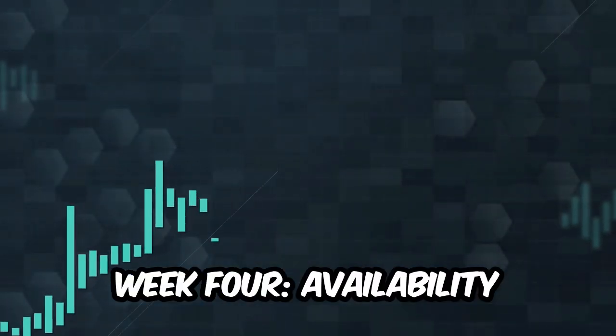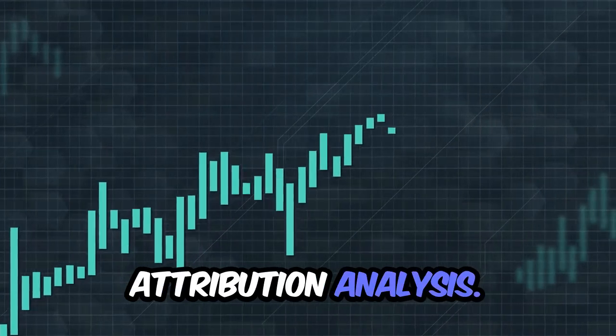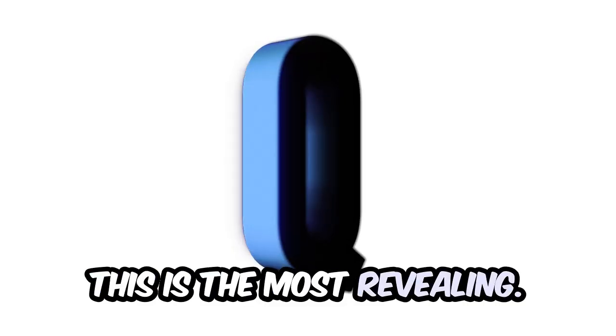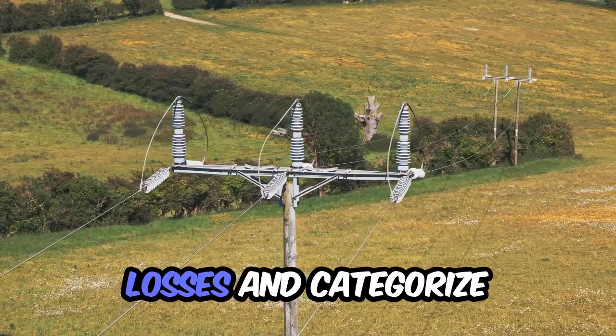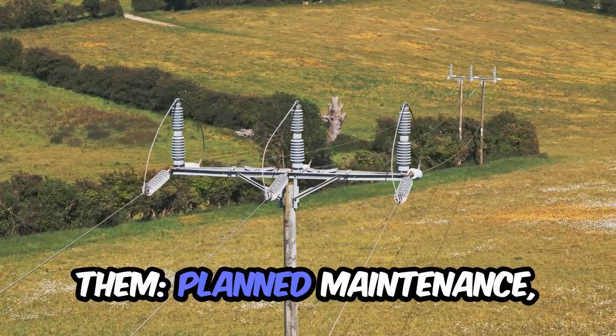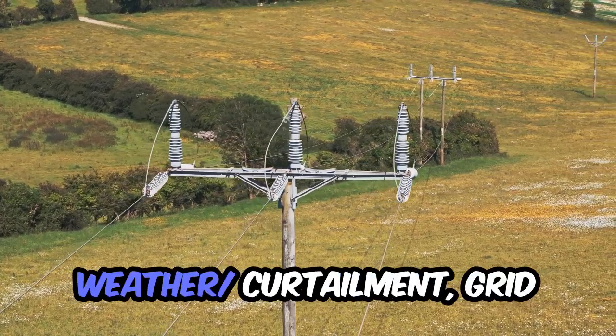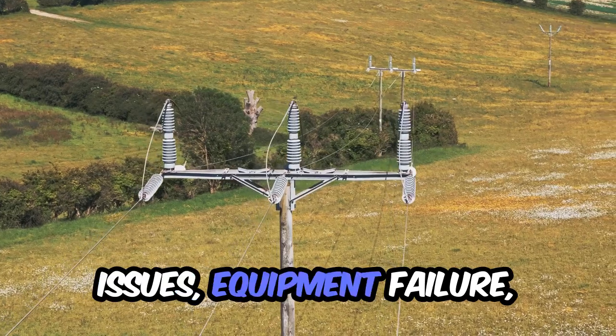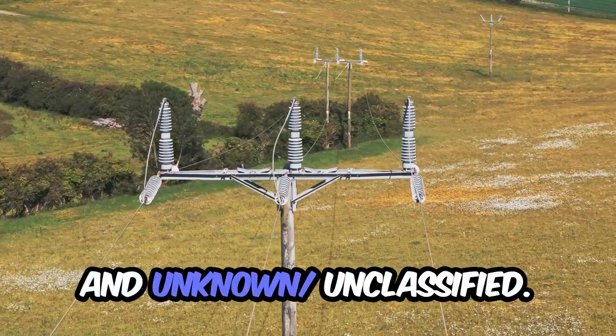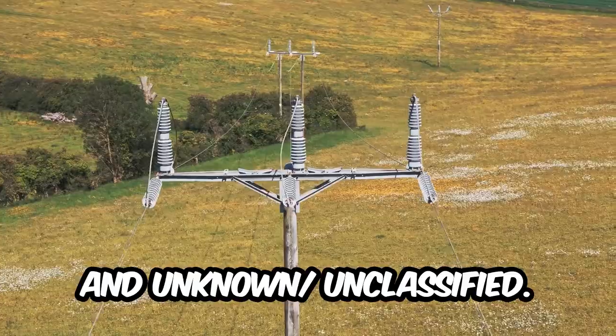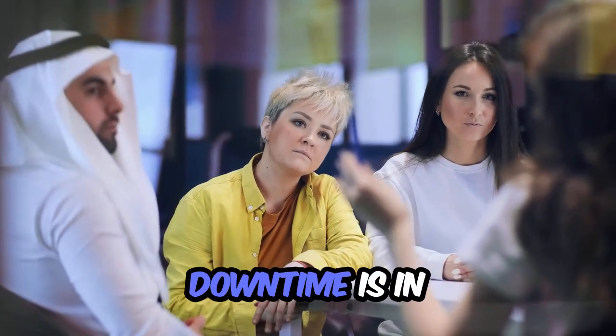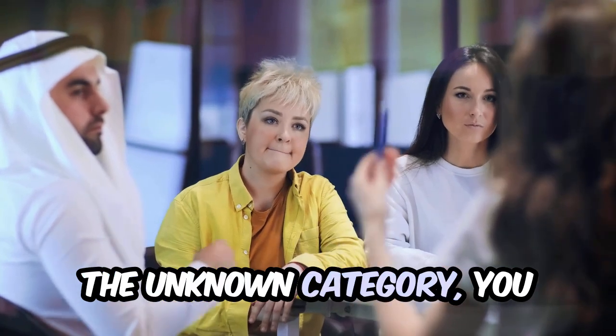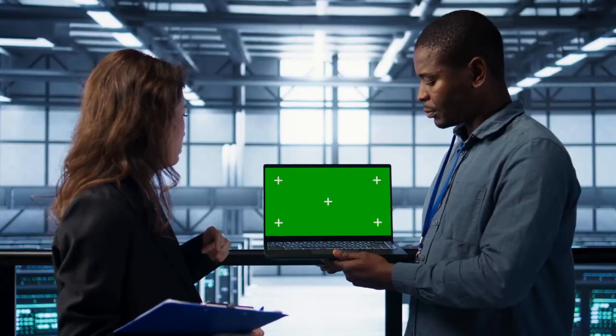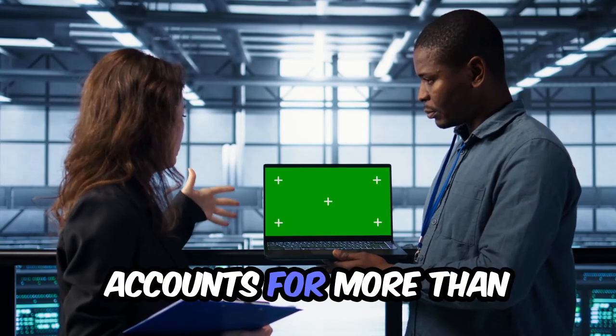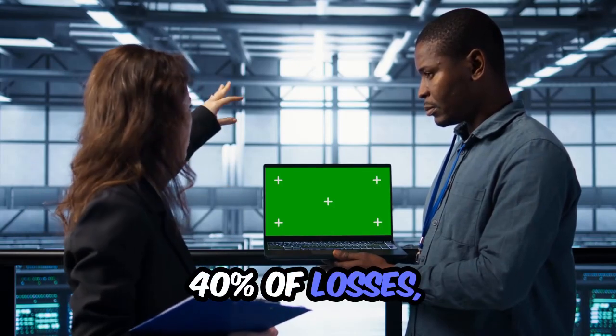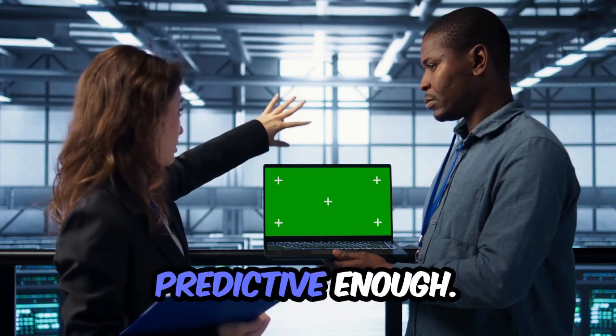Week four, availability attribution analysis. This is the most revealing. Take your availability losses and categorize them: planned maintenance, weather/curtailment, grid issues, equipment failure, and unknown/unclassified. If more than 15% of your downtime is in the unknown category, you have visibility gaps. If equipment failure accounts for more than 40% of losses, your maintenance isn't predictive enough.